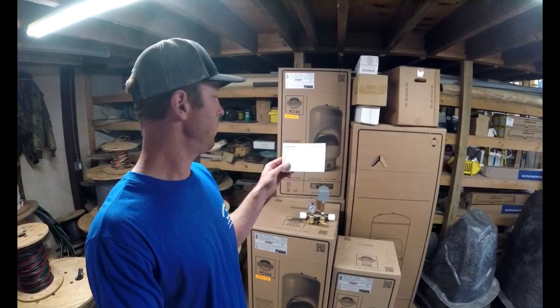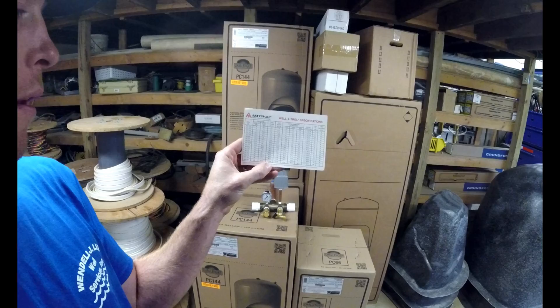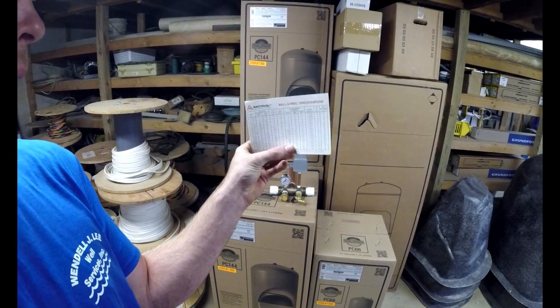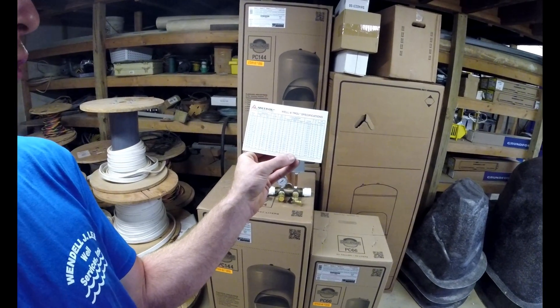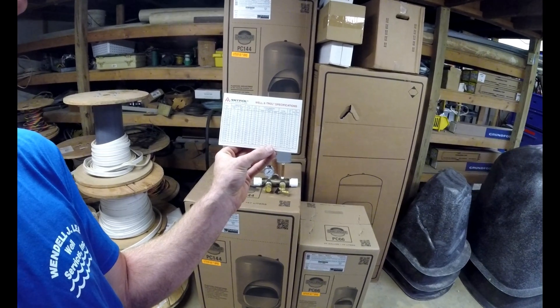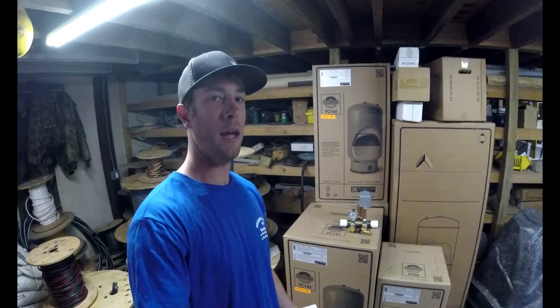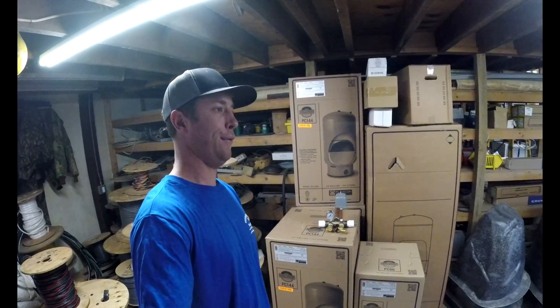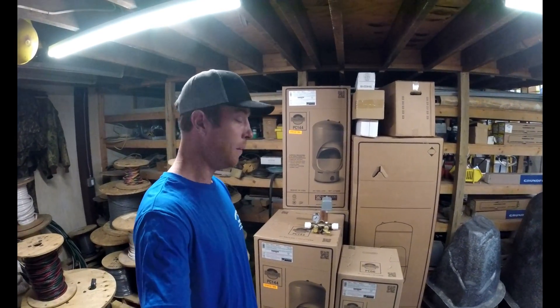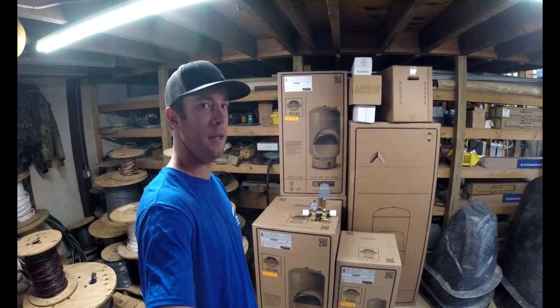Amtrol, Flexcon, and other manufacturers have charts that show this. There's one column for total volume, and then depending on your pressure switch setting, it determines what your drawdown volume is. For example, a 119-gallon tank with a pressure switch setting of 40/60 — meaning the pump cuts on at 40 PSI and cuts off at 60 PSI — has a drawdown capacity of 35 gallons. That means you'll run 35 gallons before your pump cuts on. This ultimately determines how much your pump cycles, and a pump cycling too rapidly is the number one cause of pump failure.